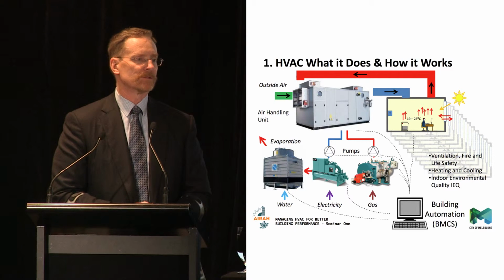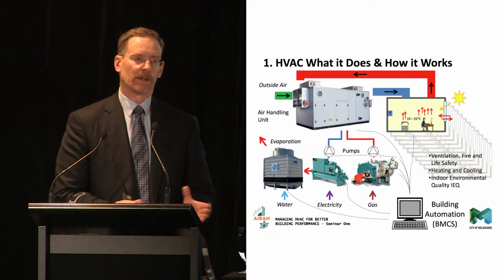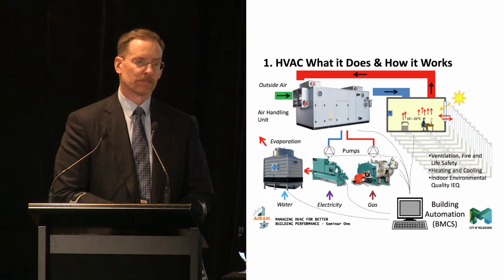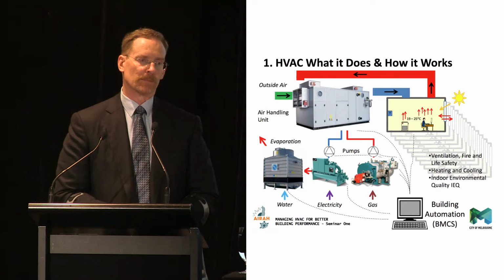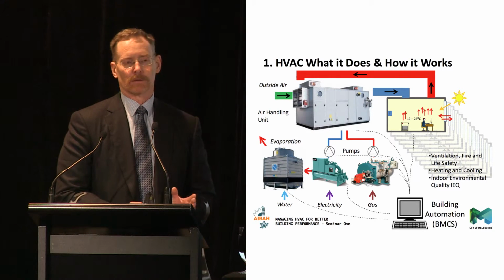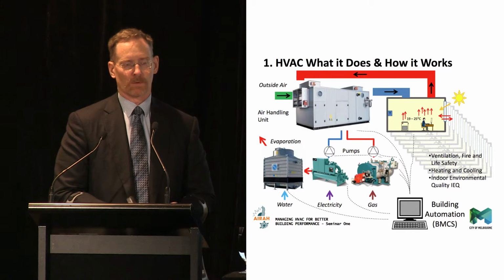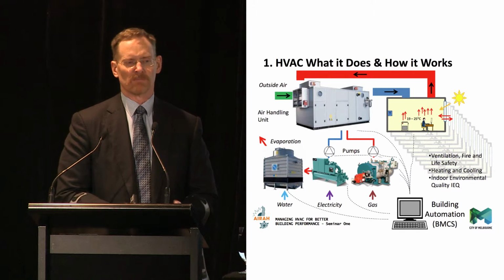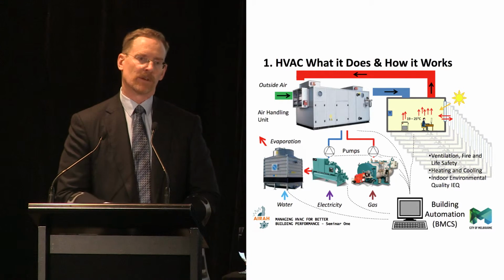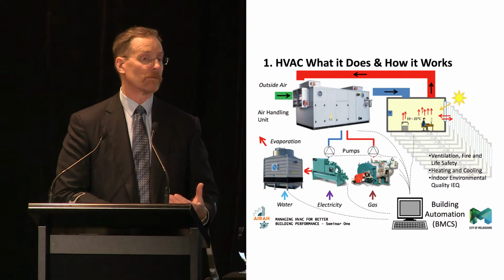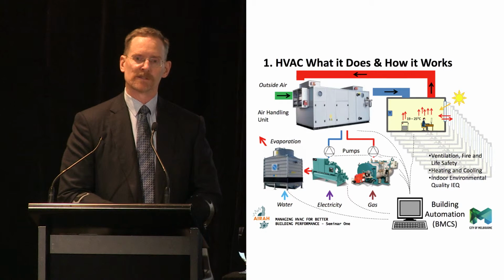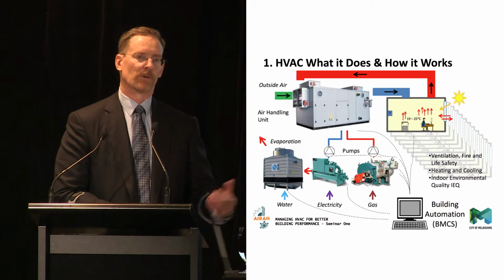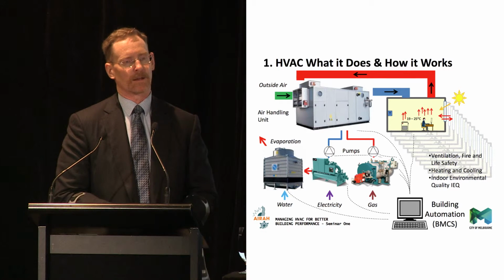If you think about a high-rise office tower and think about a floor plan and think about the heat loads. So the heat loads internally will change as people come and go during the day, but also as the sun moves around the building. So you've effectively got 5 zones in a square floor plan. You've got an internal zone where really there's not a great deal of effect from the sun. You've got a north zone, east zone, west zone, south zone. And these vary throughout the day. So you effectively have, in some sense, 5 rooms per floor as a minimal sense. Think about that in a 50-storey building. That's 250 rooms.